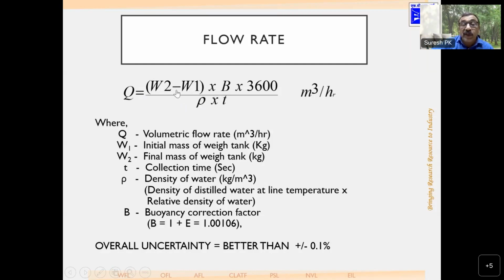Mass flow meters can be calibrated directly against mass. So this equation covers everything. Mass flow rate is covered, volume flow rate is covered, mass is covered, volume is covered. Simply eliminate the terms which you don't need and compare with the indication of the flow meter, which will give you the calibration of the meter. If there is a provision for correction of the flow meter, you can always do the correction, but you have to be judicious while doing it.